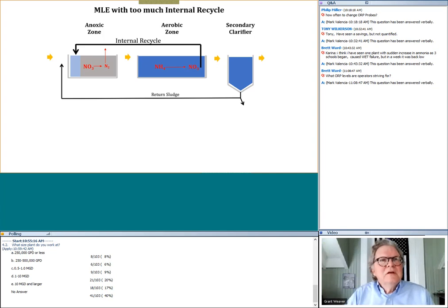By seeing what that does for you, I mean you measure your nitrates leaving the anoxic tank, which should be maybe 1 milligram per liter, maybe 2. If it's down to 0, then you can work well with a higher ORP, closer to 0 instead of minus 100, maybe minus 50. If you're getting complete nitrate removal, you can keep pushing that up until you get just a teeny bit of nitrate bleed through. Same thing on the ammonia side. If you're getting good ammonia removal at a positive 125, then that's enough air. You don't need to put in that extra 25 units of ORP.